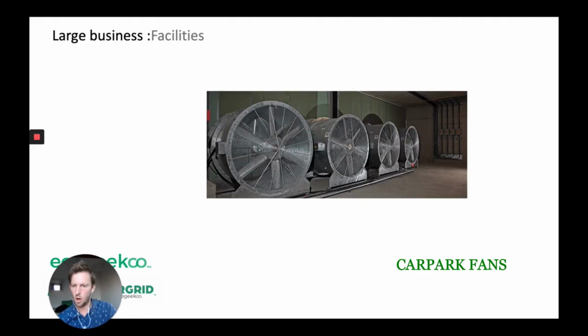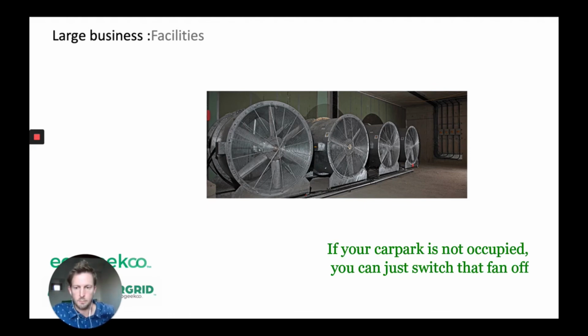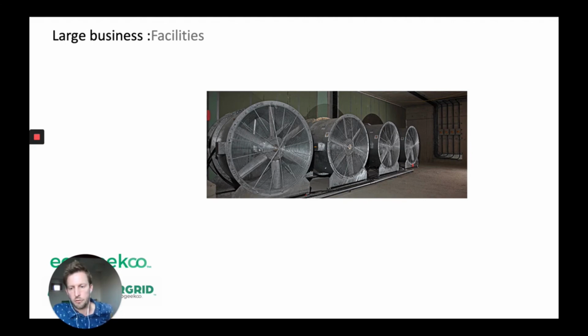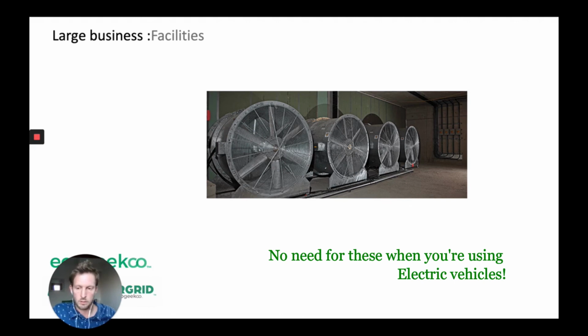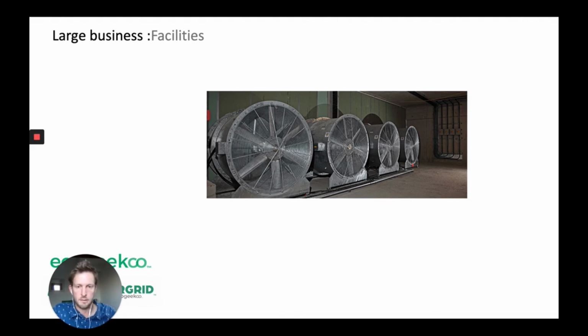The other one is car park fans. If you have basement parking, multi-story parking, or indoor parking, often by code you have to have a big fan to deal with the nasty carbon monoxide emissions that come off vehicles. That fan has to pretty much operate all the time, sucking in the air and blowing it outside where it goes to everybody else. But you don't need that. If your car park is not occupied, you can just switch that fan off and have it off for the next month whilst the building's in isolation. Unless that car park is used, you shouldn't need that fan, and you shouldn't need it when people finally move to electric vehicles, which is happening.